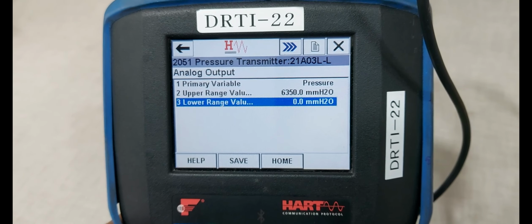Next doing the DA trim. Select number 3, maintenance and analog calibration, number 2 and digital to analog trim. Okay, we are selecting one, then OK. Connect it to reference meter. Reference meter already connected. Then press OK. Set the field device output to 4 milliamps. Then OK.